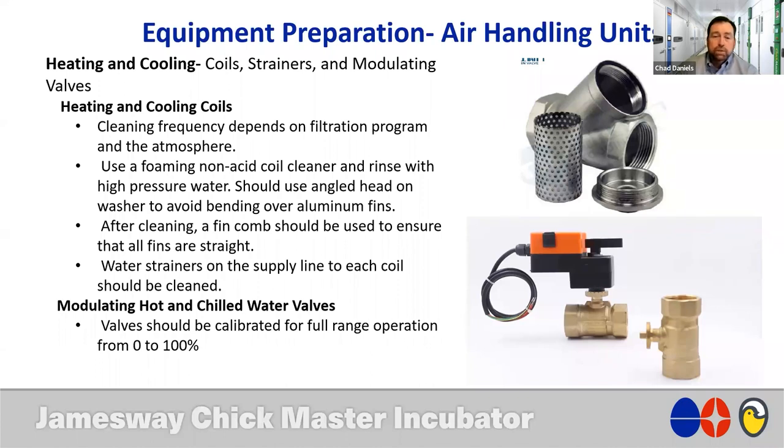I think it's important to mention that because oftentimes I'll visit a facility and I'll find a unit that is not operating at full cooling capacity, and I'll find that the actuator on the hot water valve is out of calibration. And so we're still allowing 5 to 10% of hot water flow through the hot water coil, and we're losing cooling capacity when we do that. So it's very important to make sure that these are calibrated and checked.